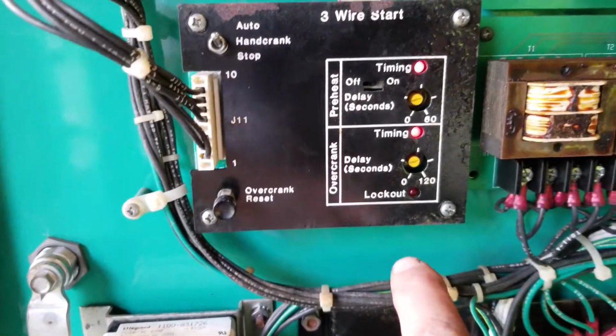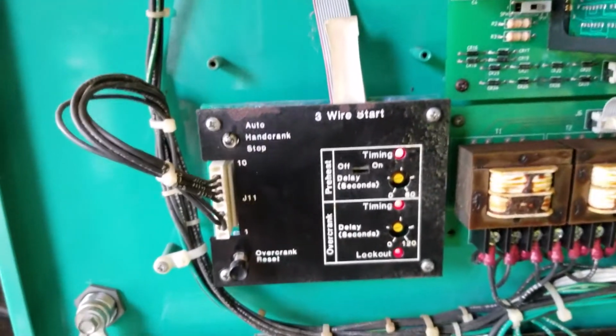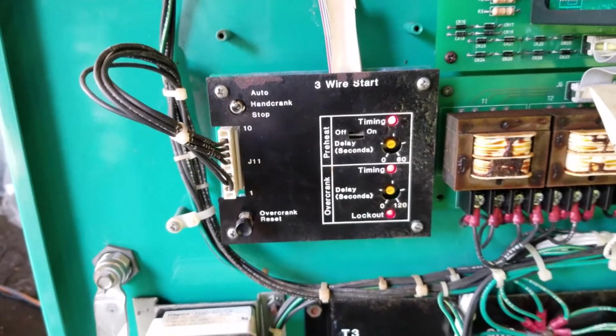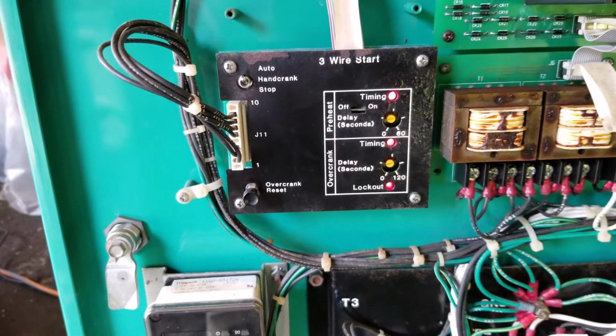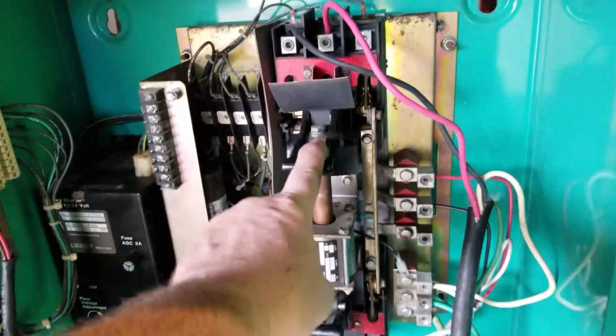In a moment you'll see the lockout light. There we go, so it didn't sense any voltage from the generator side and locked out to start. Now, do we have voltage in here? Yeah, we do. If I manually do that, you can see that's coming from the generator right there.